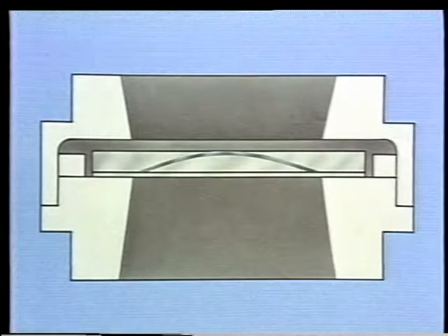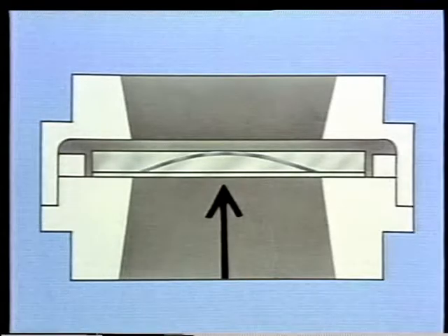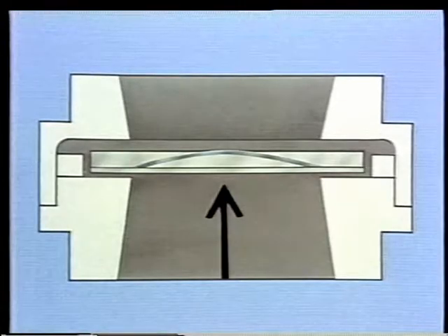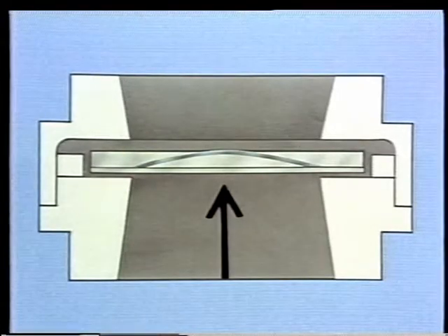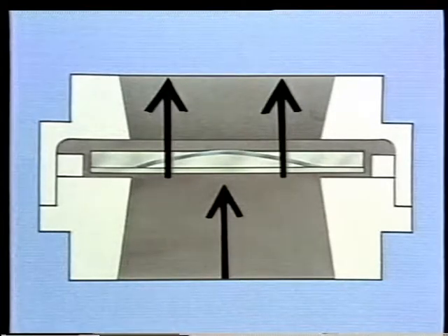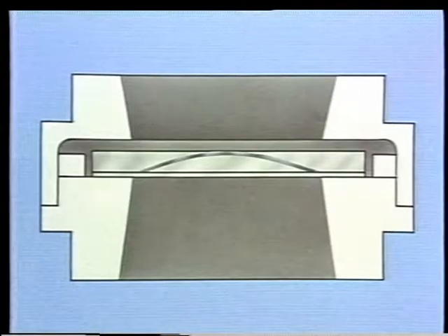Once this valve is properly placed in the casing, it works much the same as the feather and plate valves we've seen already. On an upstroke, the piston reduces the volume in the cylinder, compressing the air until its pressure is greater than the pressure in the discharge piping. Pressure in the cylinder then overcomes the discharge piping pressure and the spring tension, lifting the channel and allowing compressed air to flow out of the cylinder and into the discharge piping.